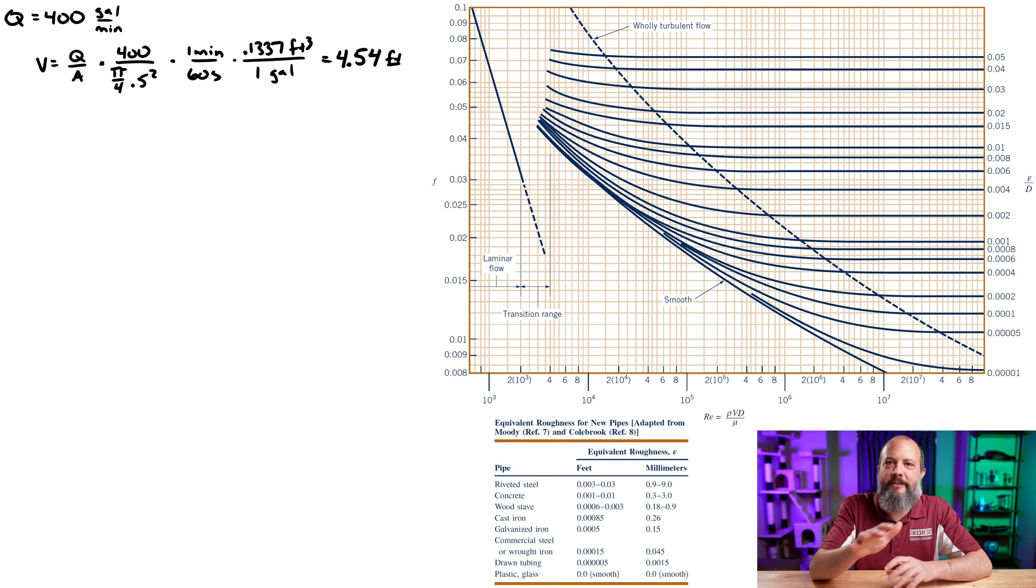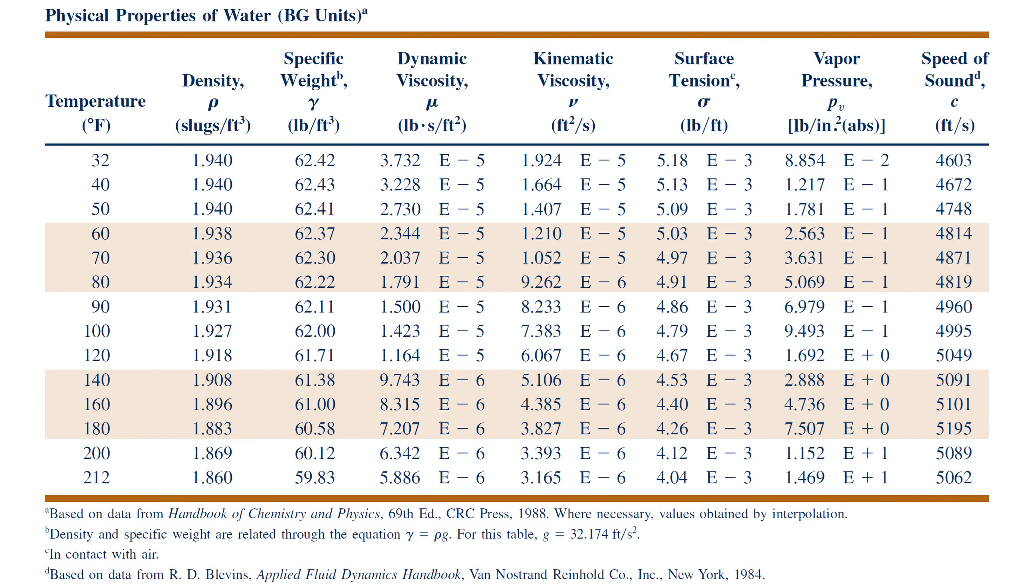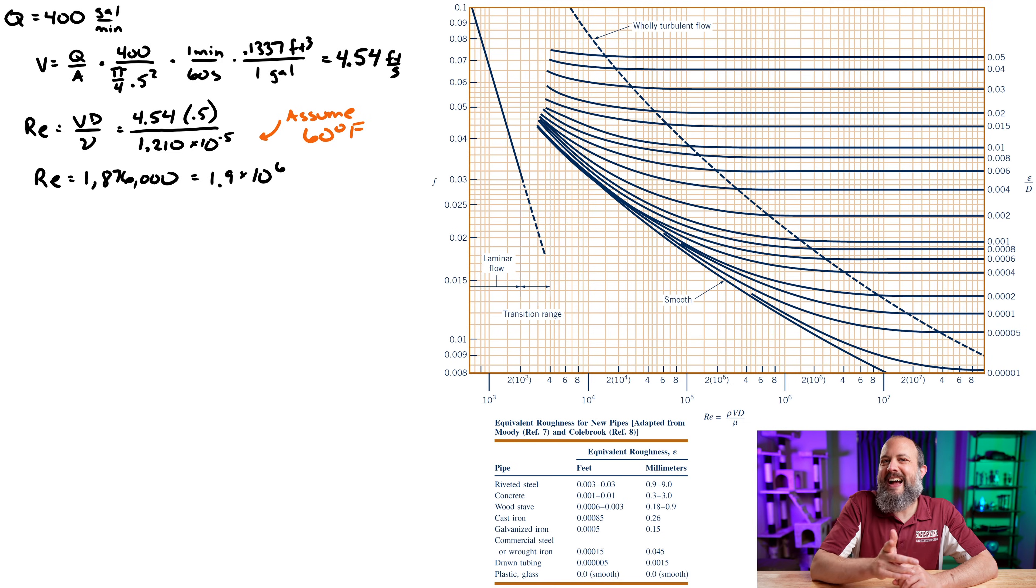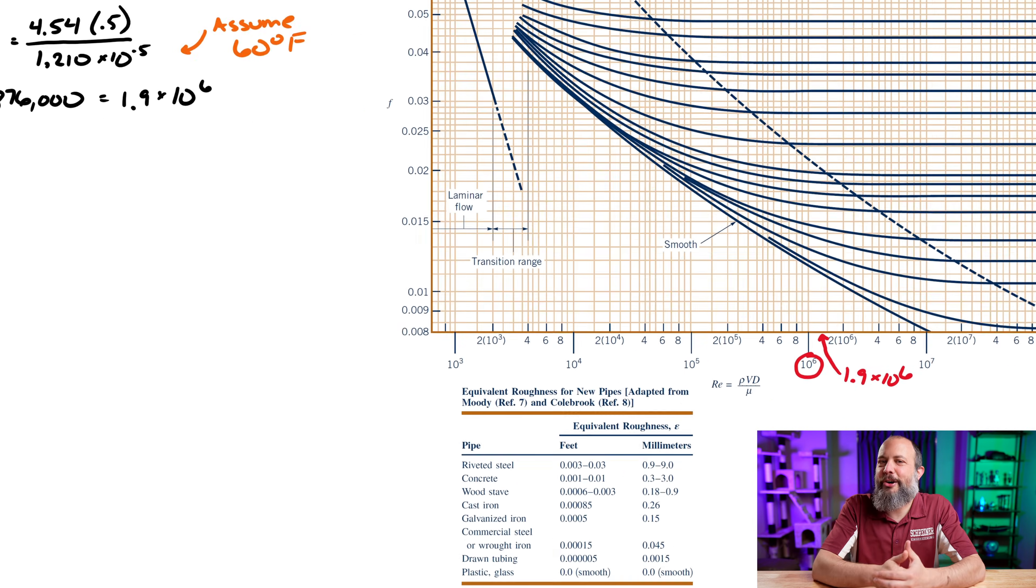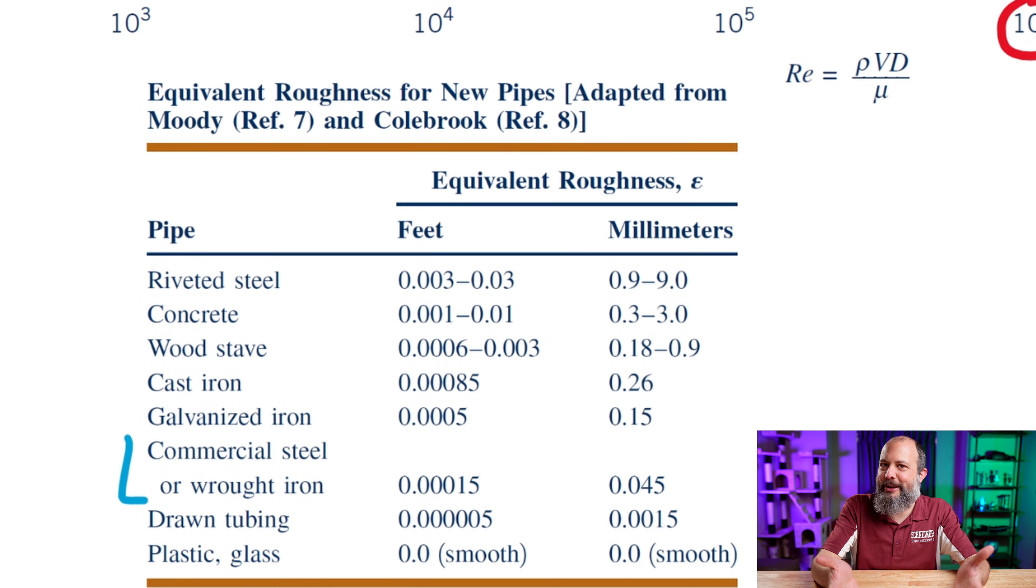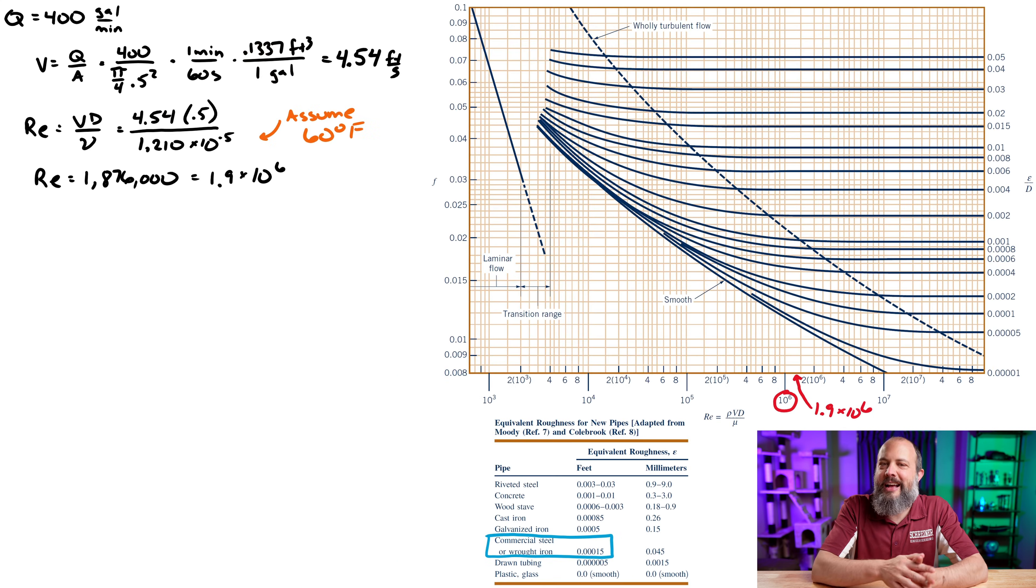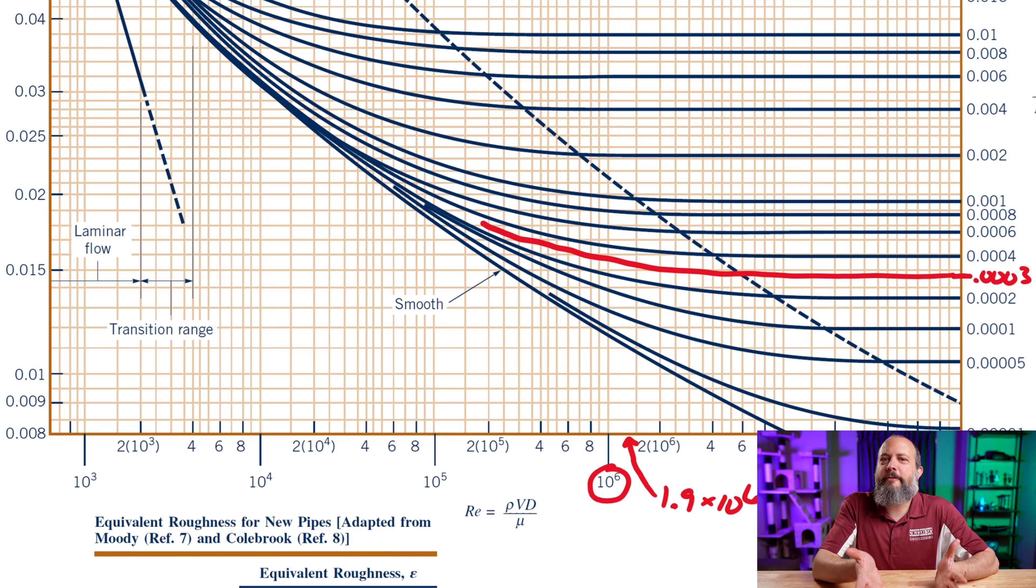400 gallons per minute, V is Q divided by A. You get a velocity of about 4.5 feet per second. Wasn't given temperature for this problem. So if I assume a standard temperature of 60 degrees Fahrenheit, I can look up viscosity. Gives me a Reynolds number of 1.9 times 10 to the 6. Also wasn't given information about what the pipe was made out of, but let's suppose we knew that it was commercial steel. I can grab the equivalent roughness factor from a table and get 0.0003 for the value on the roughness coefficient over on the right hand side of the table. So if I match up these lines, it looks like a friction value of around 0.0152.